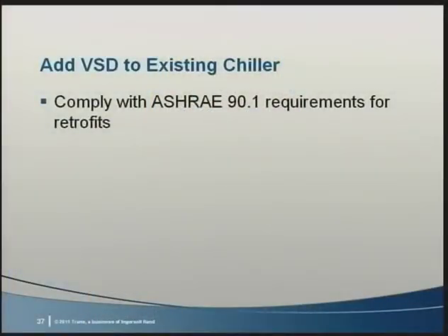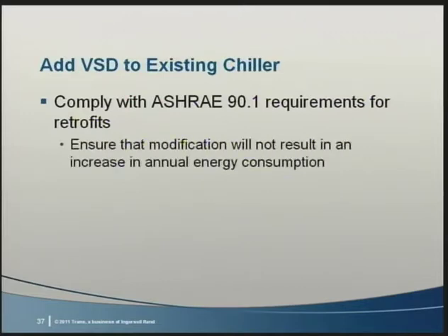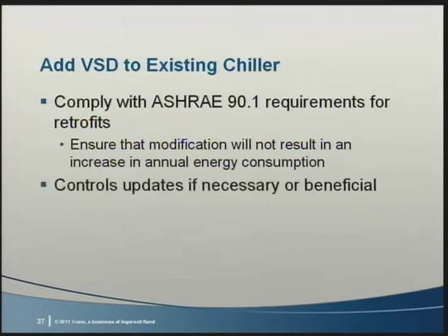Bonnie, what about upgrading an existing chiller? Well, certainly one of the most popular retrofit options is adding a variable speed drive to an existing chiller. So we'll look at that first and then discuss a few other areas. Since this is a retrofit application, we comply with the efficiency requirements of 90.1 by ensuring that the modification reduces annual energy consumption. Just like the new chiller equipped with a drive, we need to make sure that the operating conditions are such that applying it will save energy. Then we need to look at what other factors, like controls, need to be considered when completing the evaluation.